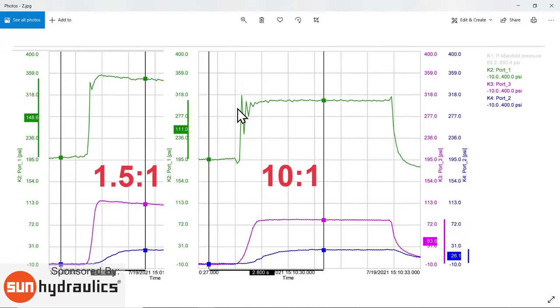But uh-oh, what's this back here at the beginning of the descent of our hydraulic cylinder? That is that instability. That is what you just saw in the 3D movie, as at the beginning of the descent, a bit of overshoot, undershoot before a balance started to occur. That moment when you let that weight free fall into gravity, there is that moment of uncontrolled acceleration of that mass before the balancing act between the pilot pressure and the port one pressure balance out against each other on the spring, and the oscillation dies down and we've got smooth control.